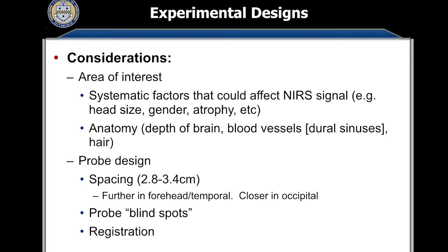But you keep the source detector pair constant. Keeping the source detector pair constant means you're getting the same depth into the brain, although that depth means more if your head is really small, in terms of fractional depth. The other side is to try to keep the positions that you're measuring from constant and allow the spacing to change. The downside of that is that with the spacing changing, you now have a signal-to-noise issue, because as the spacing gets bigger, your signal-to-noise is going to get worse.